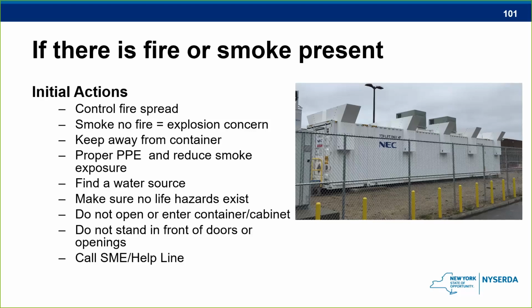Making sure that there's no life hazards. As I said before, they're not supposed to have any people in here. There's no reason to have people in here. They have the security fence. Does it mean that no one's in there? Well, guess what? I still wouldn't commit my forces in there, because if you were to put the firefighters in there with this smoky condition, a potential explosion event, and also all that stored and stranded energy, even though you shut the power down, open bus bars, you're really not doing justice to the firefighter in that situation. If these doors aren't open, you better assume that there's no one in there, right?